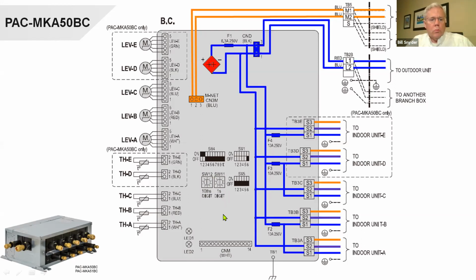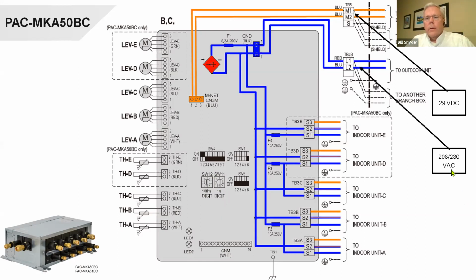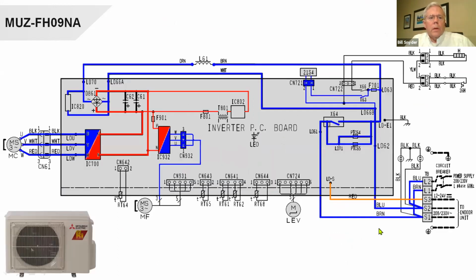Okay, so much for that. Again, we got 29 volts here and line voltage here. Okay, this is an MUZ-FH, again, an outdoor unit. This happens to be a heat pump. L1 and L2 come in here for line voltage, and S2 and S3 are your DC voltage. It says 12 to 24 volts, bouncing around type voltage here.